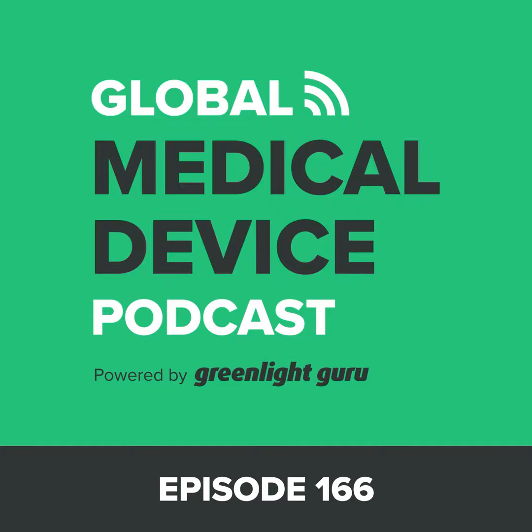What is FDA suggesting and recommending in this guidance? So I have just three or four specific comments and suggestions based on what I thought was important in the guidance. The first one is FDA is asking manufacturers to include a list of all of the materials that we use in our device that in this case have either direct or indirect contact with the skin, and a statement confirming that the list of those materials has a documented history of safe use in a legally marketed medical device in the United States. Those are very easy words to say, John, but what do they mean in reality? In other words, how do we show that?